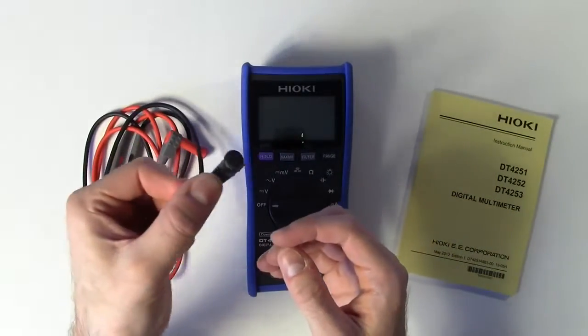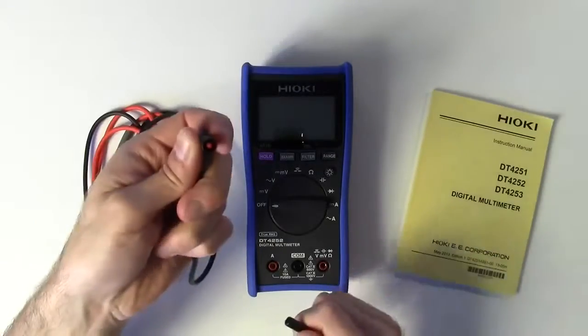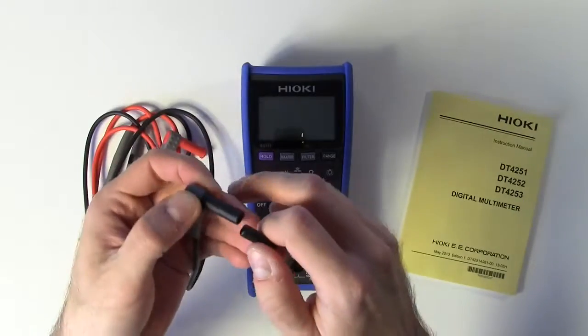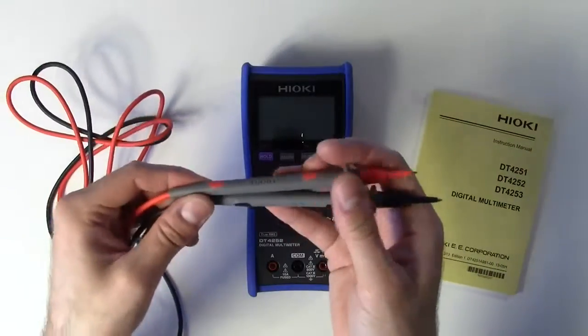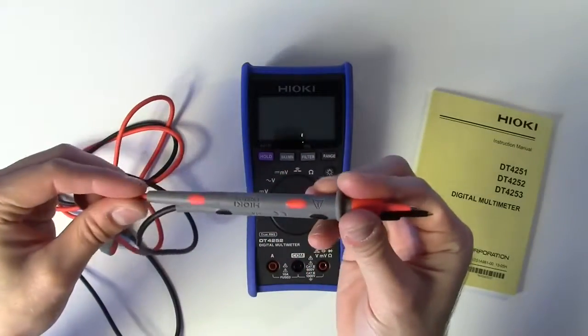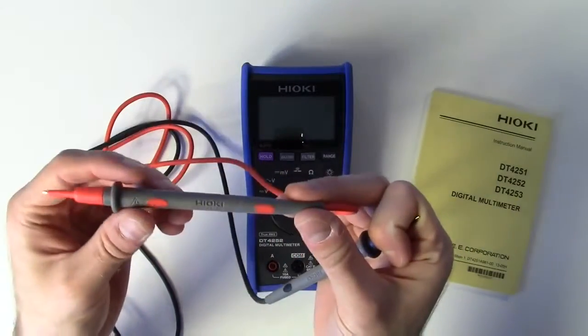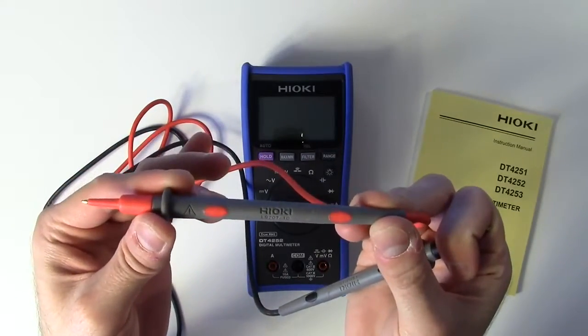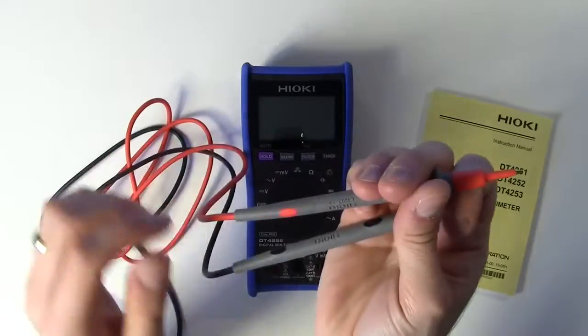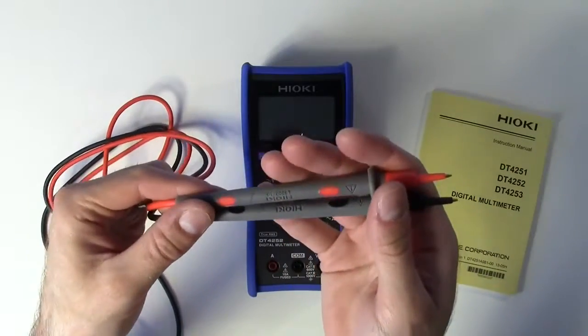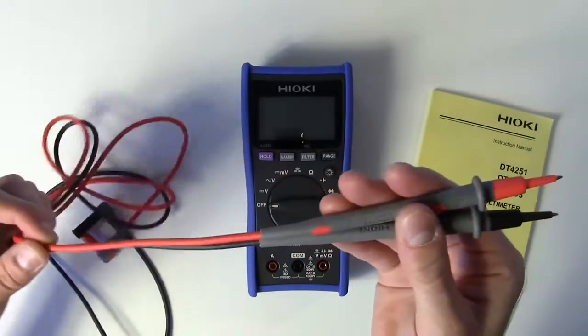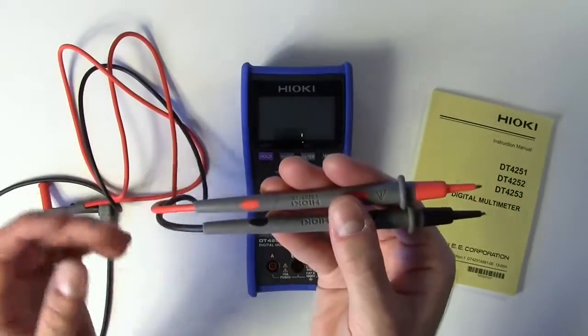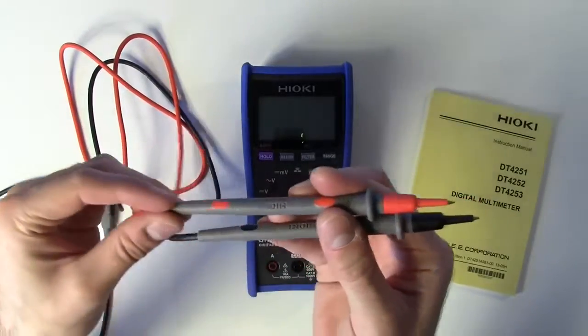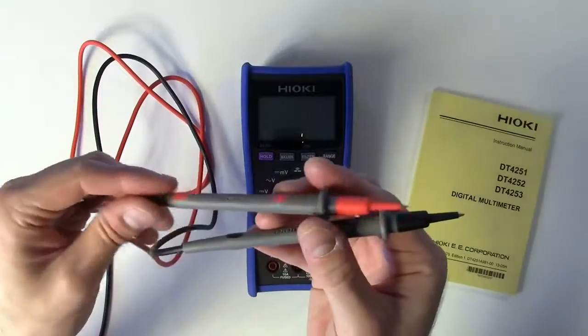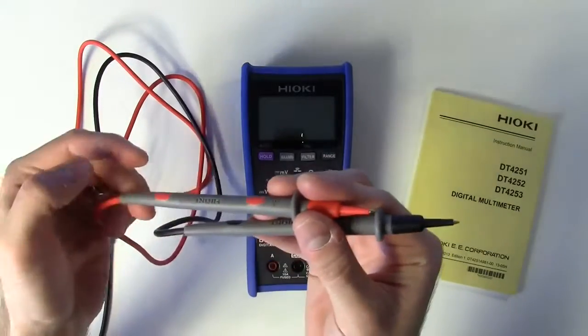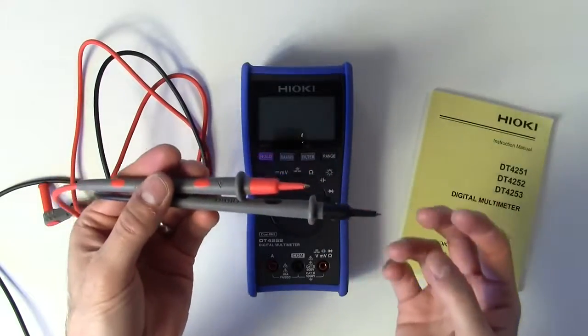And a nice little touch that I noticed is that they include these little plugs to cover up the banana end for when you're not using the test lead. I think that's just a nice touch there. The actual probes themselves feel very good quality, fully rubberized along the length with the Hioki logo. This particular probe is part number L9207-10, color-coded, of course, and I believe these do conform to the new regulations about test leads. There are some new ones that took effect, I believe, in 2013, about having color coding and bicolor in order to show wear, if the wear on jackets or the test probes themselves. So you see when the second color shows through, that means you're getting deeper into the insulation.